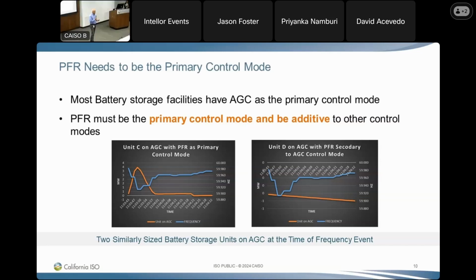Well, when you look at this graph, look at the unit on the left. Look how beautiful that response is in relation to the frequency. If you were to look at a hydro or a thermal unit, you'd see a delayed response. Now, the actual frequency response period we look at under BAL-003, I'm not directly involved in that process, but if I'm not mistaken, it starts from 4 seconds out to 30 or 40 seconds out. So my tool over here goes around 40 seconds or so, and that's what I look at.